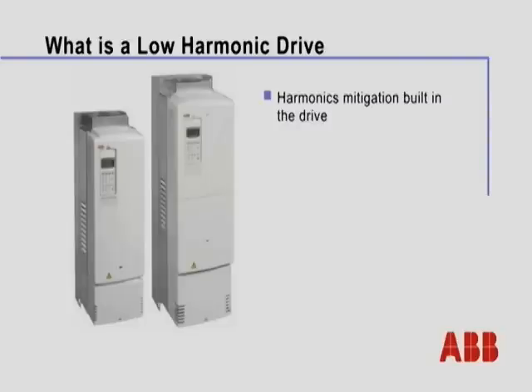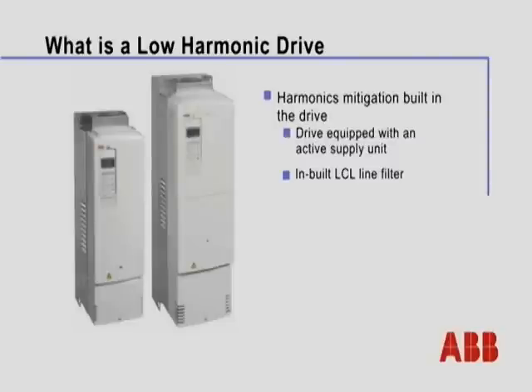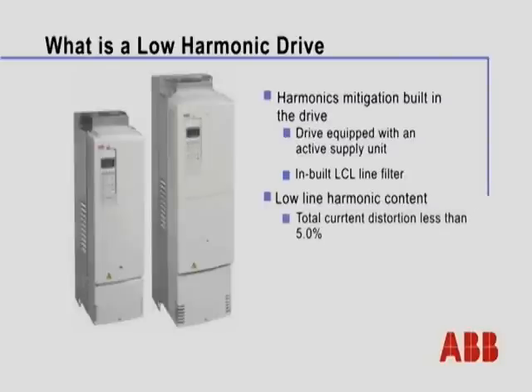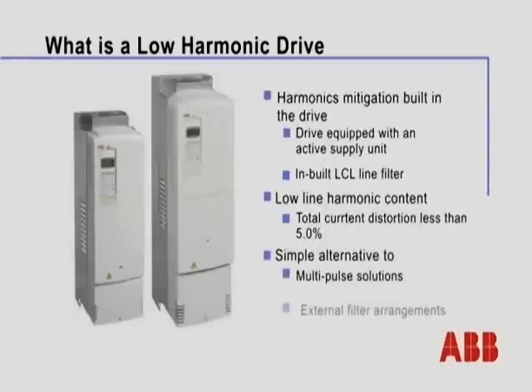Instead of using the typical 6-pulse diode bridge, we're using an active front end and an LCL filter. These two items are contained inside the unit and in combination provide a low harmonic content to the AC line, typically less than 5% regardless of the distribution system. This provides a simple alternative to multi-pulse solutions, which oftentimes use external filter arrangement.